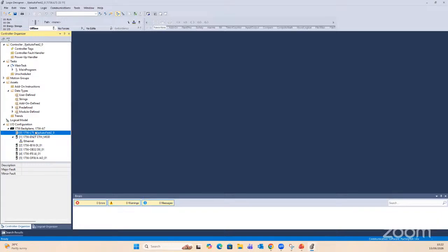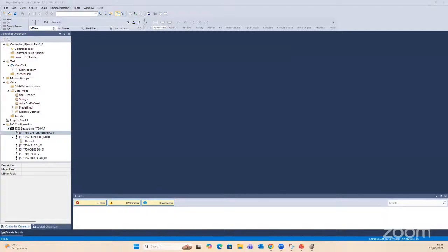Okay. For me to use the emulator, why is my emulator not opened yet? For me to simulate, I have to run my emulator and I need to change the PLC in my program file to an emulator. Because what Studio 5000 does is that whatever device you put here, that's the device it is actually looking for on the network. If it can't find that device, it won't connect to whatever else is there.